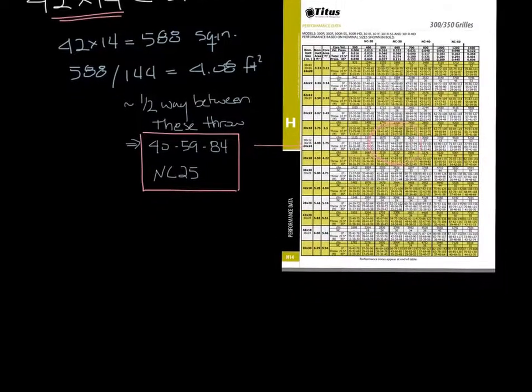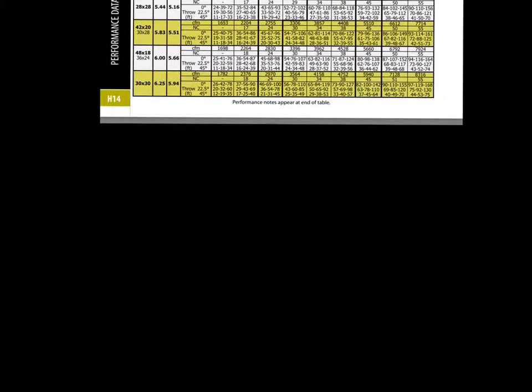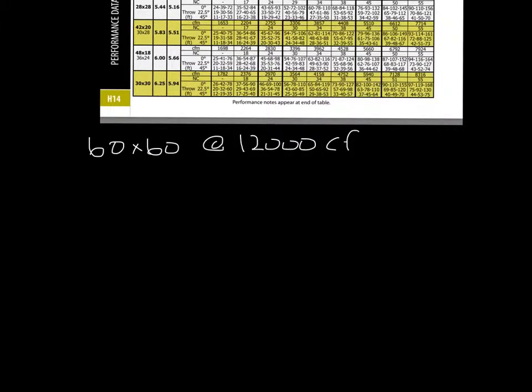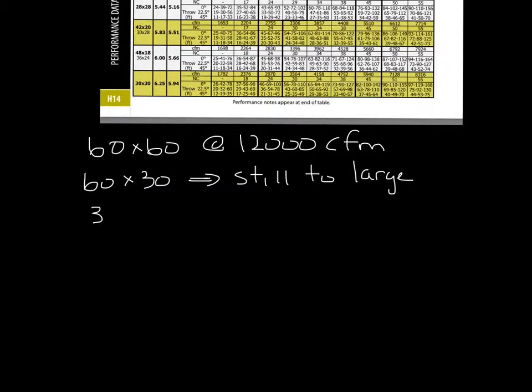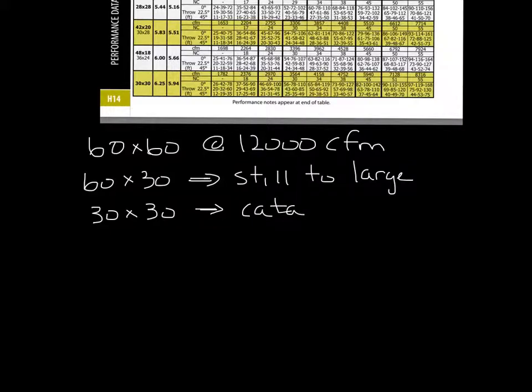We catalog up to 48 by 48 inch grills, but let's say you need a 60 by 60 grill at 12,000 CFM. What you need to do is basically cut the grill in half until you come up with a size that is cataloged. If you take the 60 by 60 and call it a 60 by 30, it's still too large for the catalog, so let's go down to 30 by 30 — and this is cataloged.